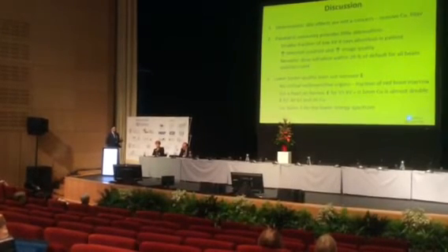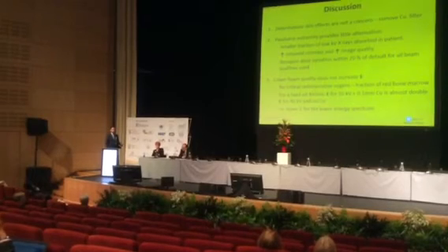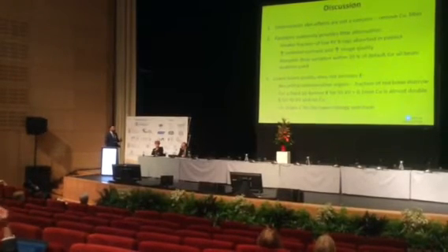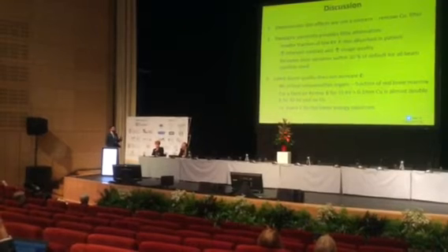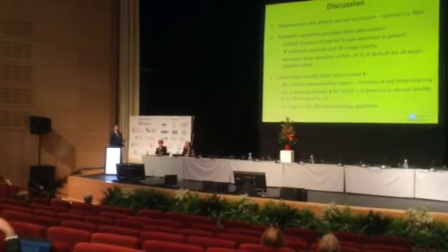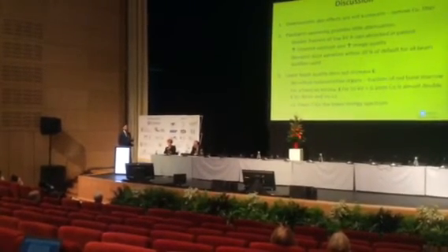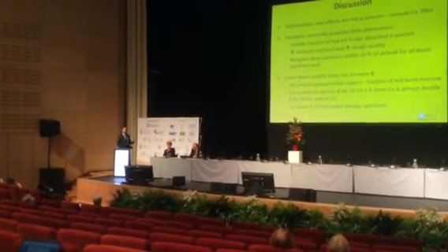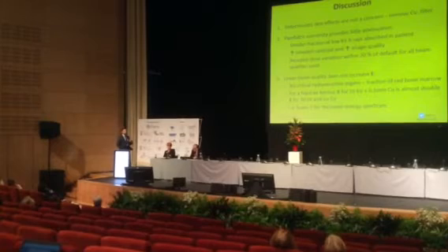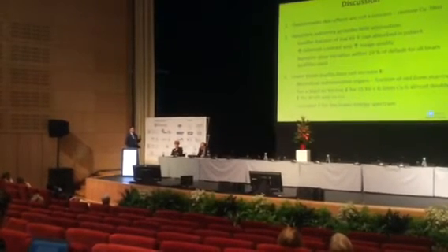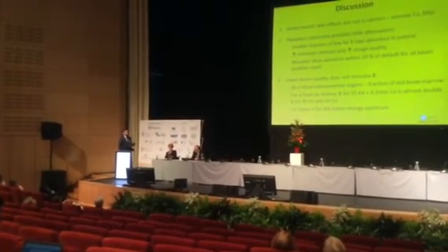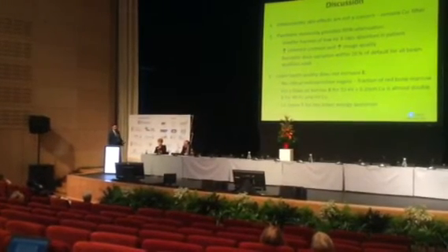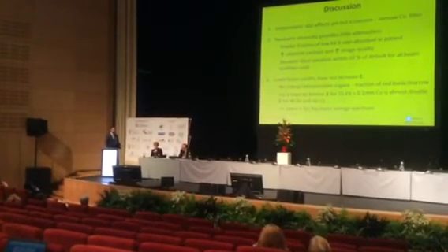So the old European guidelines encourage this additional copper filtration for the majority of paediatric projections. However, a paediatric extremity offers very, very little attenuation, and there are no major superficial radiosensitive organs in an extremity. So therefore, removing this copper filtration actually didn't increase the skin dose. It actually gave us a better image quality because more of the photons were able to contribute to the image in a positive way, and therefore improve the inherent contrast and give us better image quality.